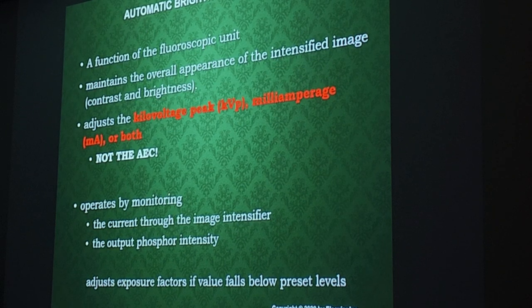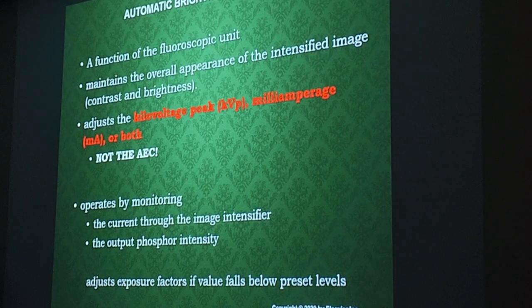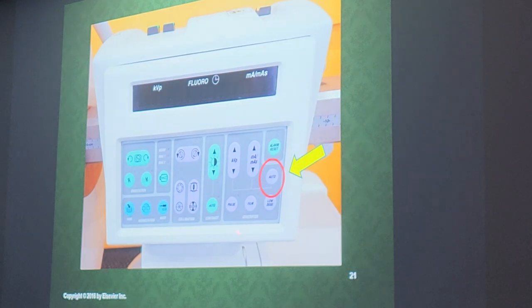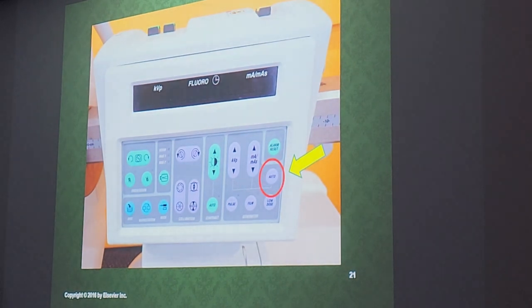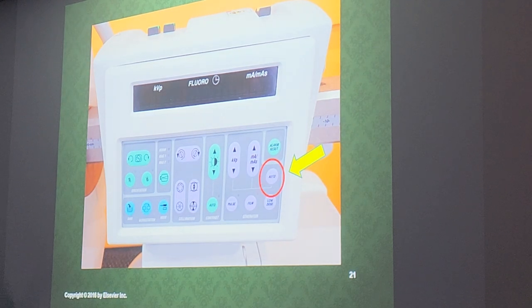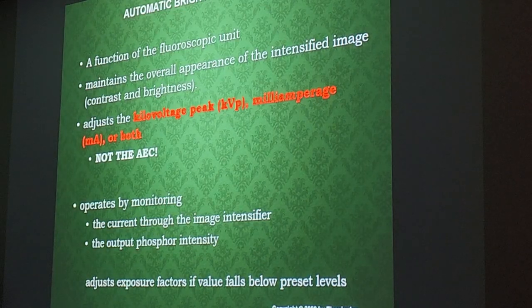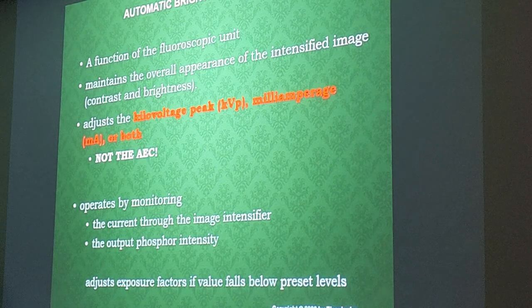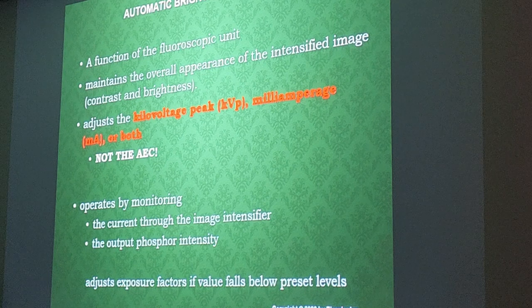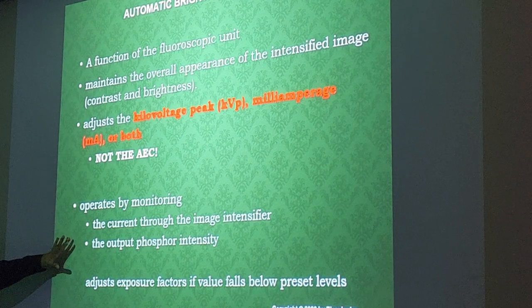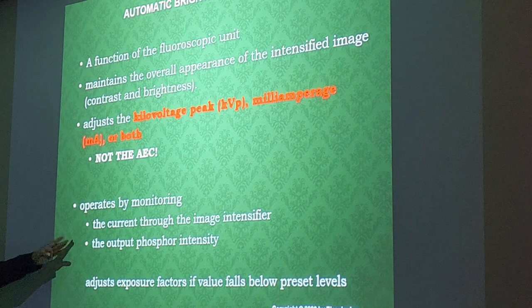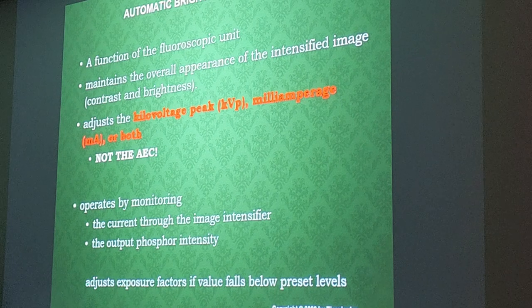Our fluoro systems and C-arms have something called ABC — automatic brightness control. Typically if techs have the auto button on, they're not manually adjusting the kVp or mA — it sets it for you. ABC helps maintain the overall appearance of the image by controlling contrast and brightness, and it adjusts the kVp, mA, or both. It works by monitoring the current coming through the image intensifier and the output phosphor intensity.